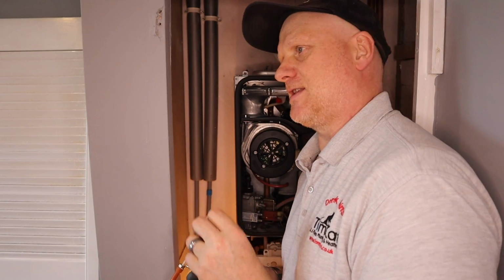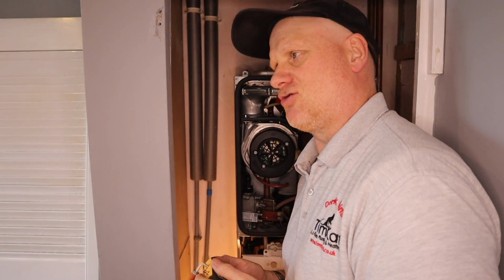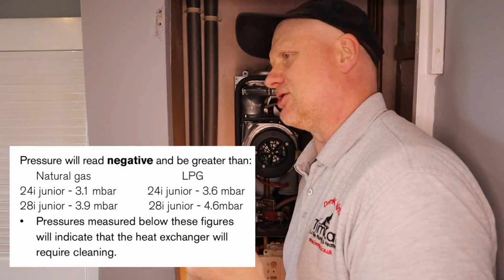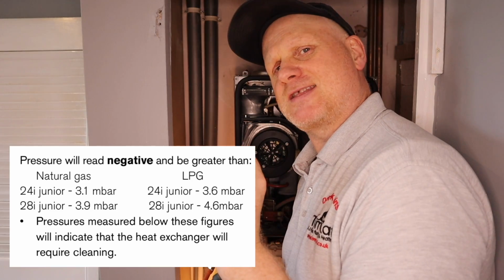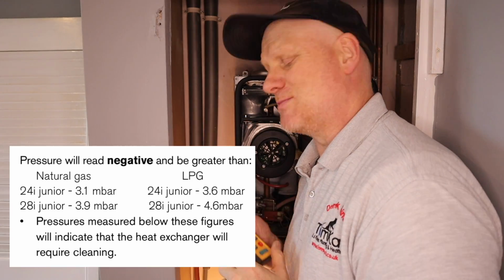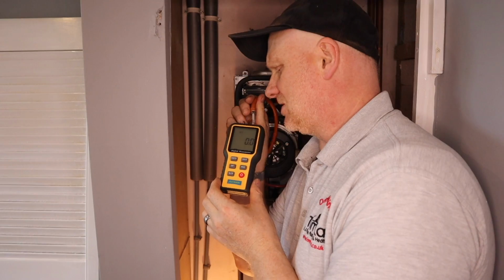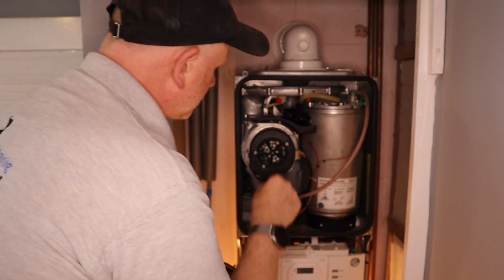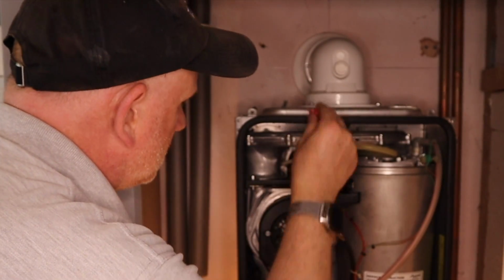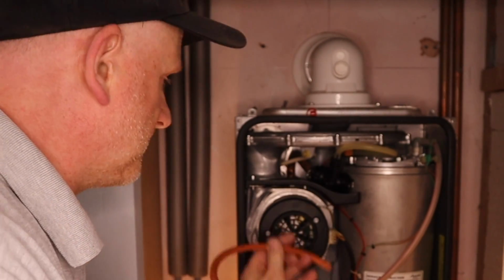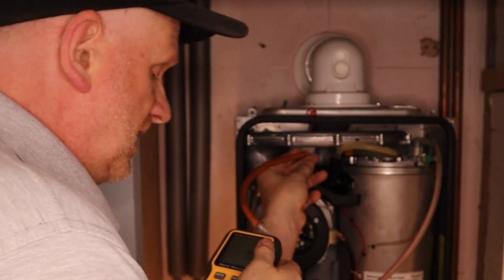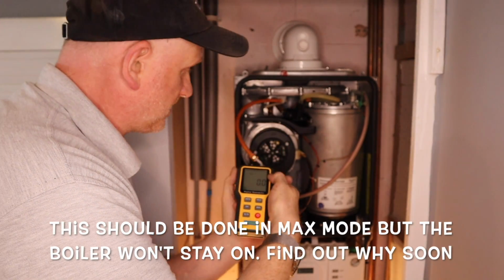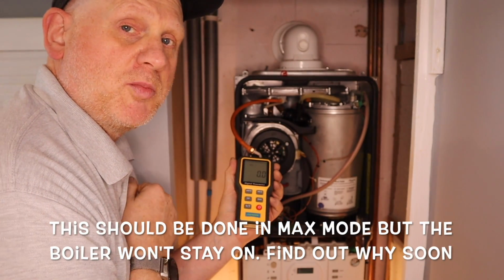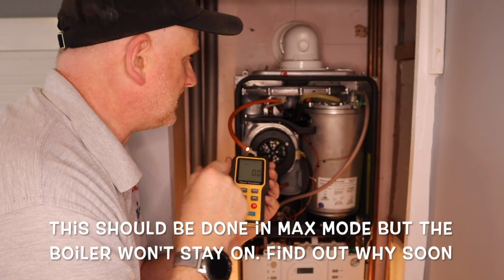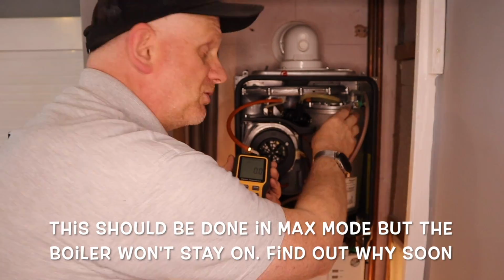And what this does is it allows us to see whether the heat exchanger needs stripping. Now, this is an LPG 28i Green Star Junior, and it needs to be greater than minus 4.6 millibars. So I've got my little digital manometer, and what I'm going to do is remove this cap like that. I'm going to place this over there like that. I'm going to turn the hot tap on, and I'm going to see whether I get less than 4.6 millibars reading on here. Now if I get more than 4.6, it means I don't need to strip this.